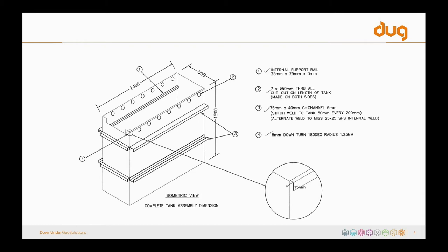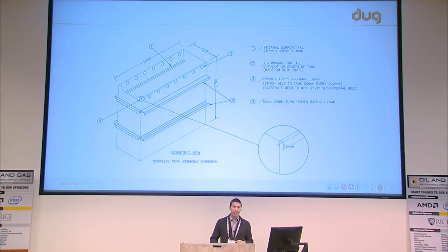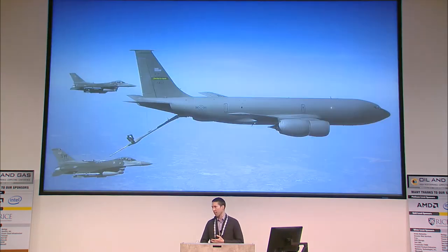Not every aspect comes for free—we do have to fill this room with dielectric fluid. To put that in perspective, we needed 500,000 liters of it. A KC-135 aerial refueling tanker holds about 112,000 liters, so we'd need four of these to fill that first room. It's 500 IBCs worth turning up at the facility. But even with all that fluid and the custom-designed tanks, all in, it's cheaper than a standard high-end water-chilled door type rack—very cost-effective before you even start talking about density and those benefits.